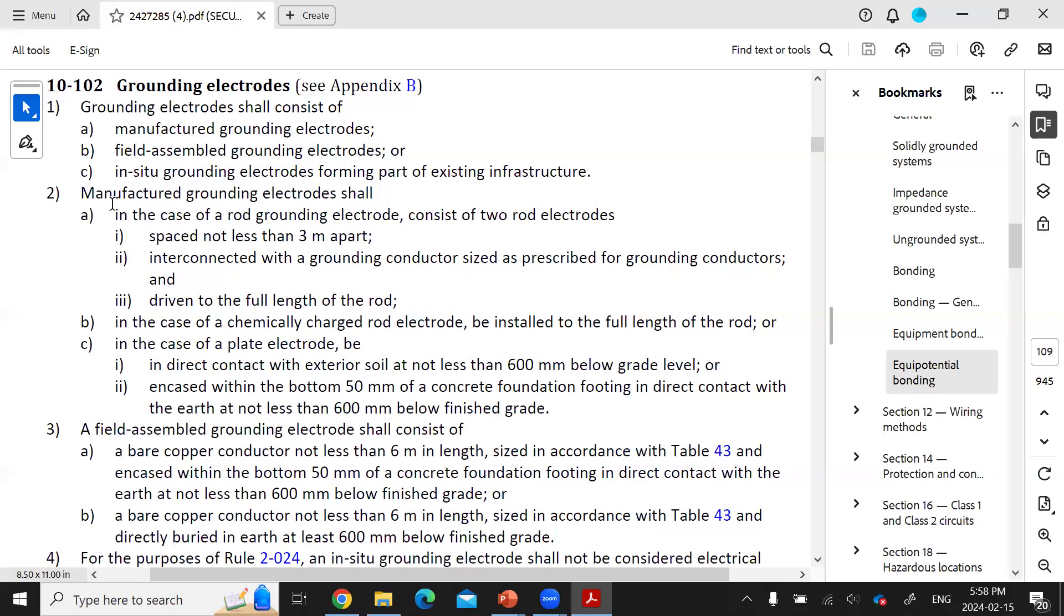Section 2 of Rule 102 says that manufactured grounding electrode shall, in the case of a rod grounding electrode, consist of two rod electrodes that are spaced not less than three meters apart. Those rod electrodes have to be at least three meters long and also driven into the earth to their full length and spaced not less than three meters apart, so they don't interfere with each other.